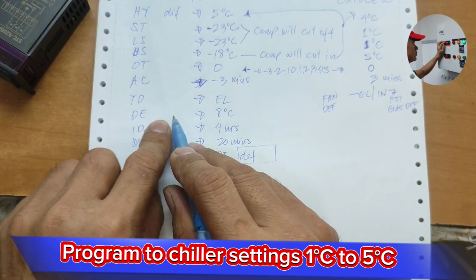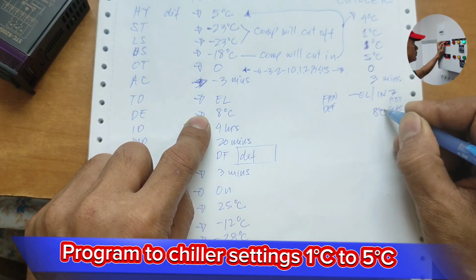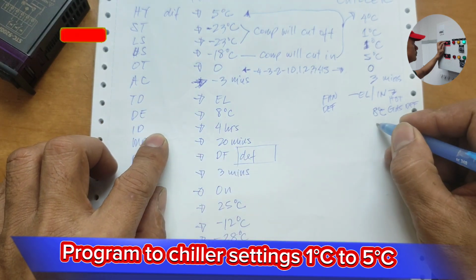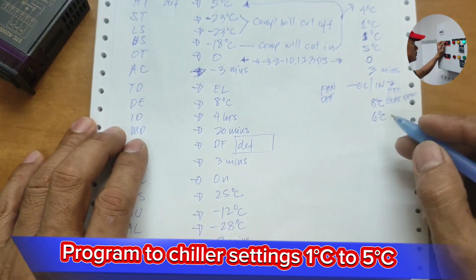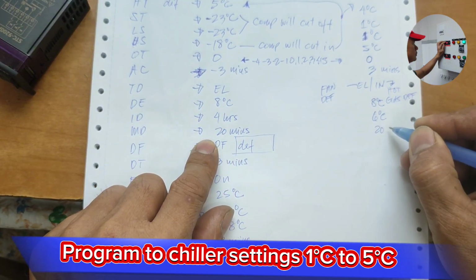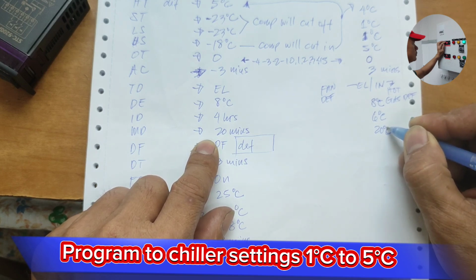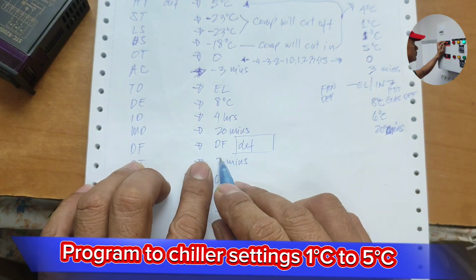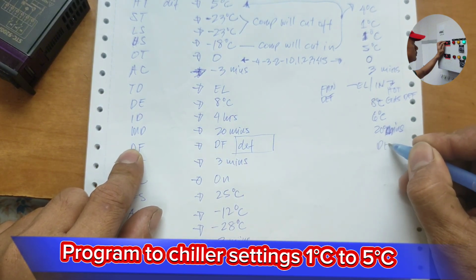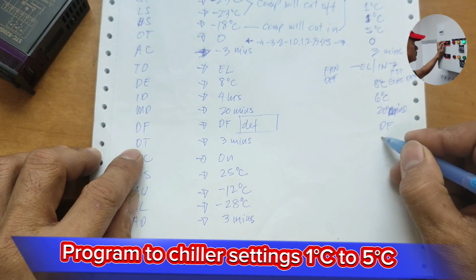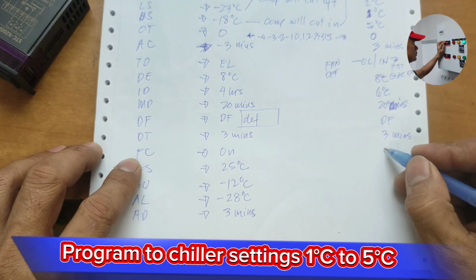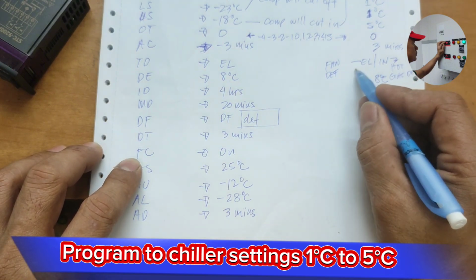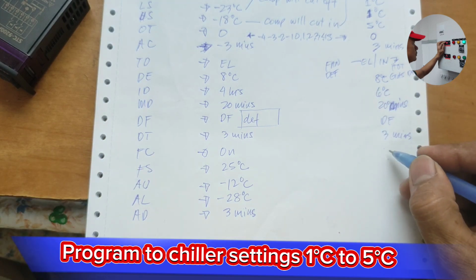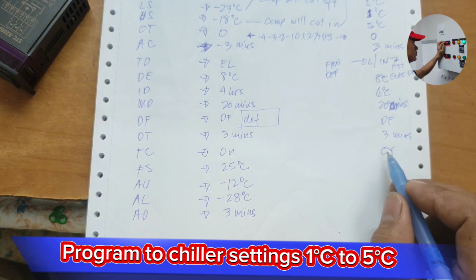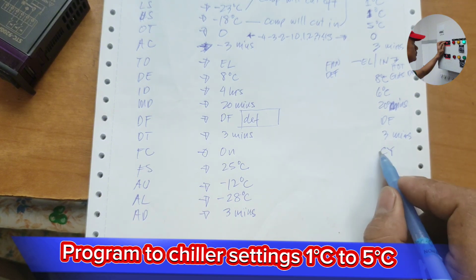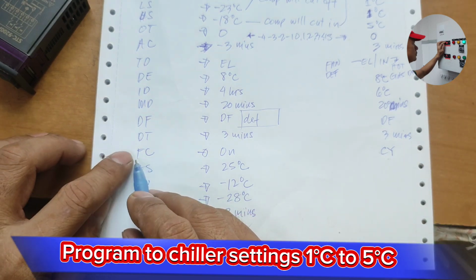And for the defrost termination, same, just choose 8°C there. For the defrost cycle, choose 6, no problem with the 6, every 6 hours it will defrost. For the MD, you can go 20 here guys, 20 minutes. And for the DF label, just go for DF again, and the same 3 minutes for the dripping time. For the FC, if you are in fan defrosting, you should choose CY, evaporator fan runs with the compressor on during defrost. Take note guys, you should choose CY for FC.